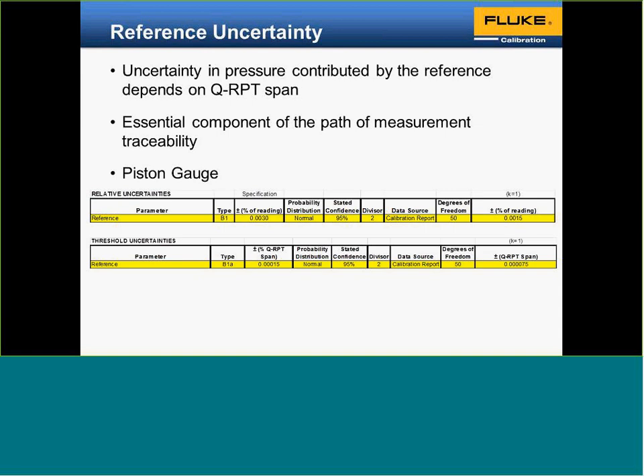In the table, I have a relative portion and a threshold uncertainty portion. Here I have a relative uncertainty, which is B1, of 0.03% of reading, from the calibration report, and I divided because that's 95%, to get the last column on the right, my K1, my one standard uncertainty.